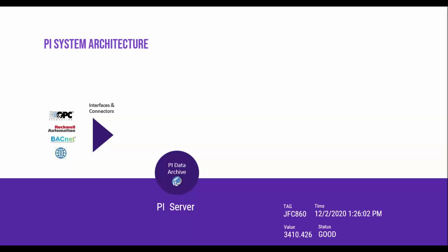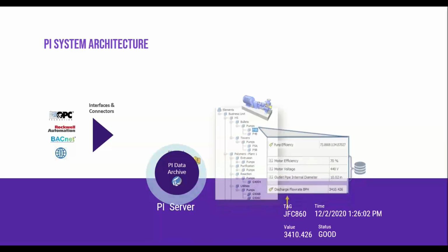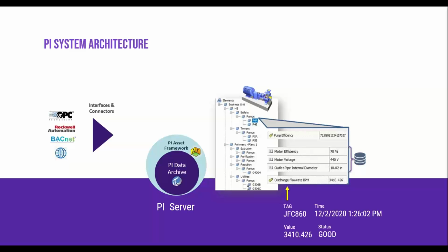As an example, we have a tag here, and the tag doesn't mean anything on its own - I don't know what JFC means, but in a second I'll show you the power of the PI system. The next layer of the PI system is the PI Asset Framework, usually called AF. Here we give context to this tag. So the tag JFC, which we didn't understand, now, just by looking at the asset framework, we can see it's a discharge flow rate. This makes it easier for an operator, or even someone unfamiliar with the plant, to understand what the reading is about. This is one of the greatest things the asset framework gives us - context for the plant.